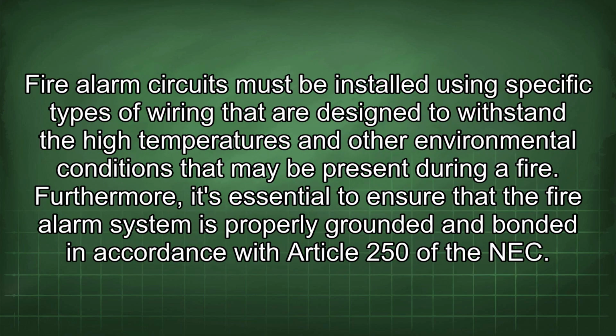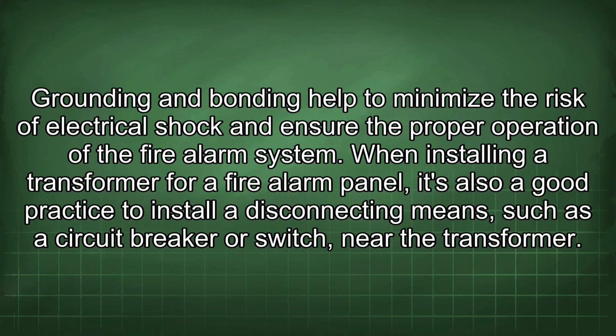Fire alarm circuits must be installed using specific types of wiring that are designed to withstand the high temperatures and other environmental conditions that might be present during a fire. Furthermore, it's essential to ensure that the fire alarm system is properly grounded and bonded in accordance with Article 250 of the NEC. Grounding and bonding help to minimize the risk of electrical shock and ensure the proper operation of the fire alarm system.